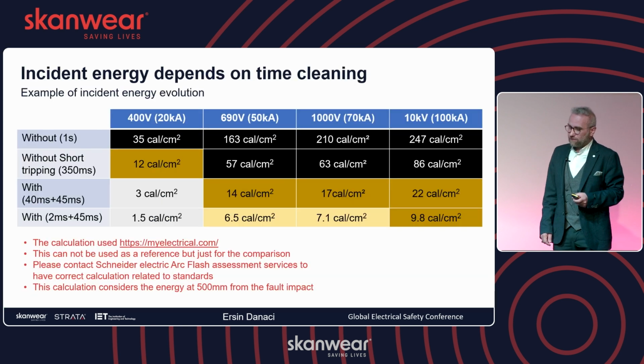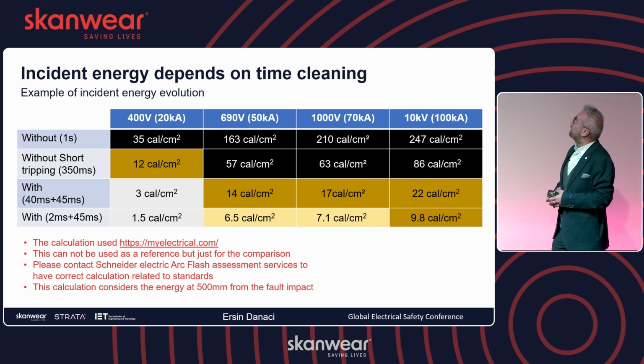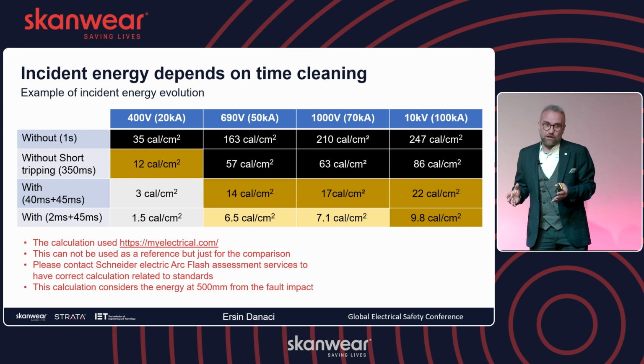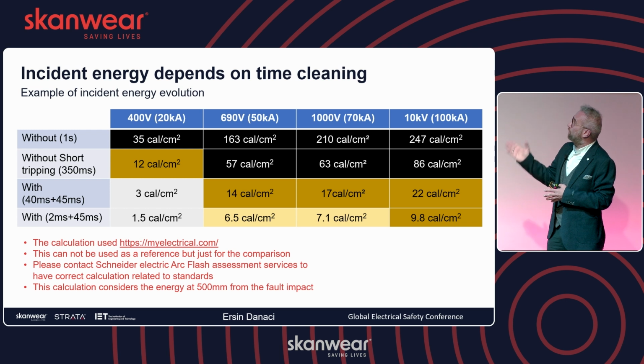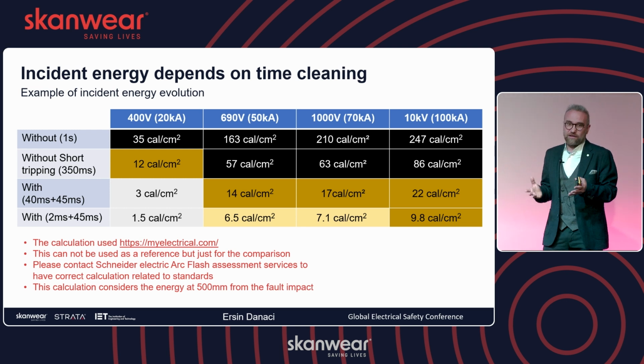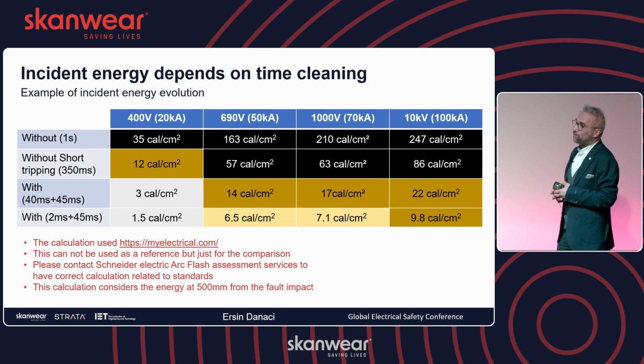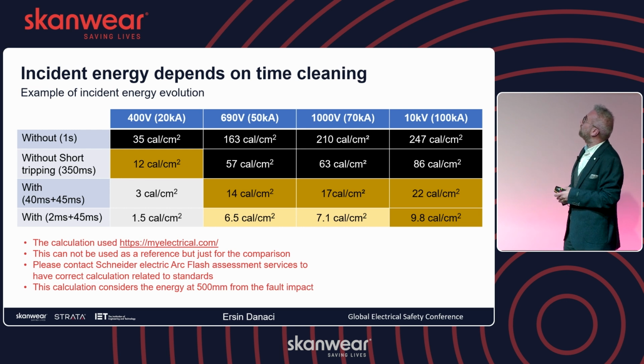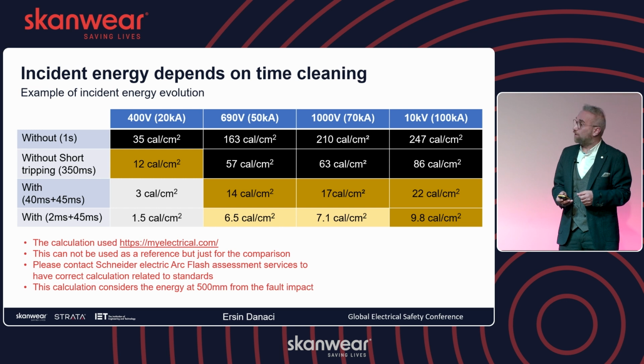So in this chart we have different calculations regarding voltage level and time. On the top column, you see that when the voltage level is increasing, power flow increasing, obviously the energy and the calories are increasing. And on the left-hand side, as you can see, when the time is decreasing, the energy is reducing. This again highlights that on the first instance of the explosion, it will give the highest damage. That's the reason, again, we need to clear the faulty circuit as soon as possible. As you can see, there is a color code here. The color code highlights how important it is to utilize the arc flash technologies for the high energy sections.